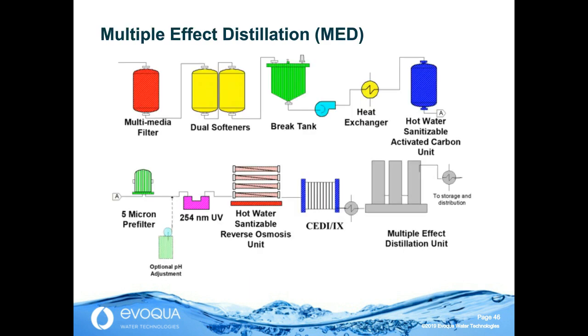They operate much hotter than VC. They can have chloride stress corrosion, silica scale, hardness scale. So multiple effect stills typically have extensive pretreatment. In many cases, the still feed system is making water for injection quality, and that has been proven in many studies. So potentially, the feed to the multiple effect is producing WFI, but the presence of a typically extensive membrane system is going to add to the capital and operating economics.